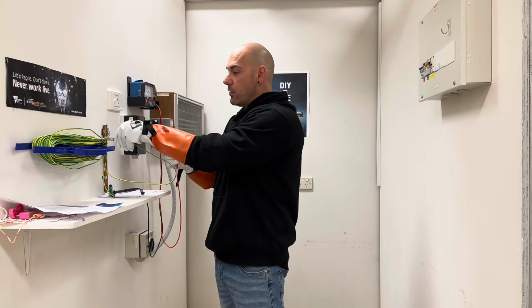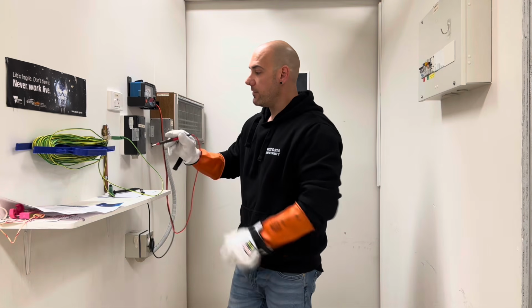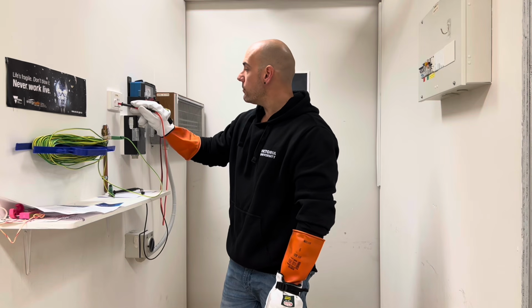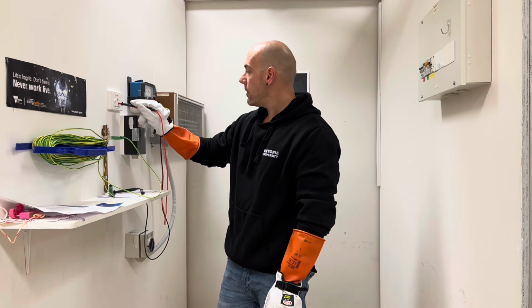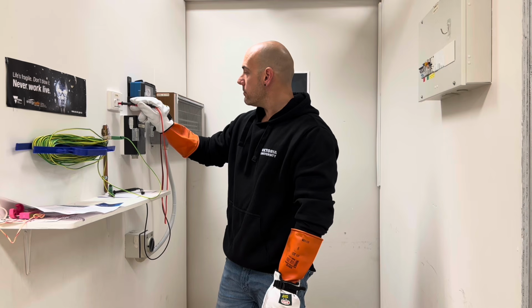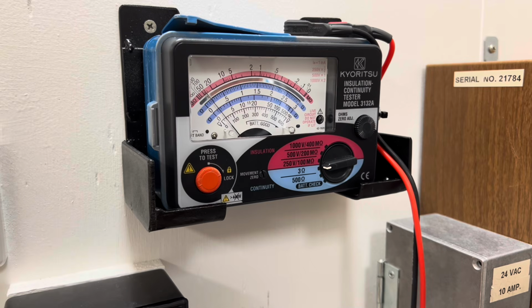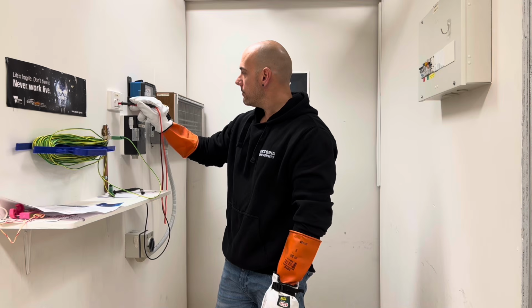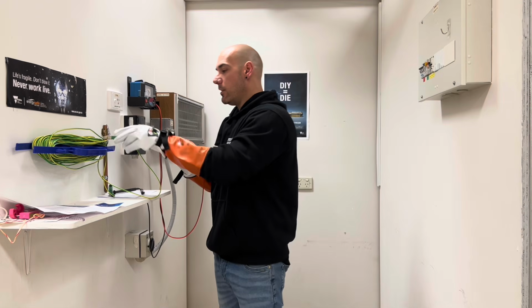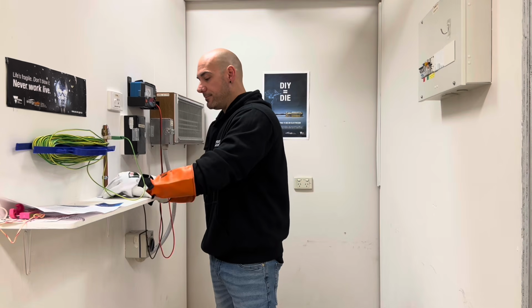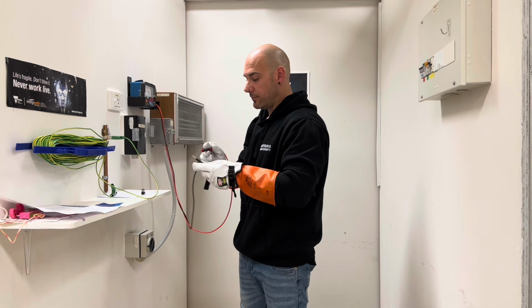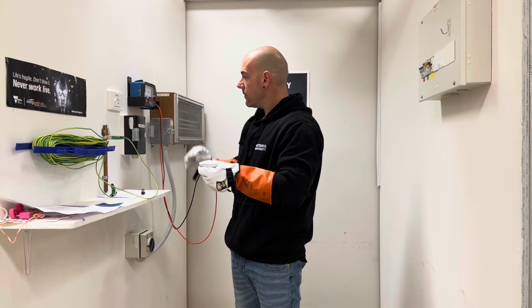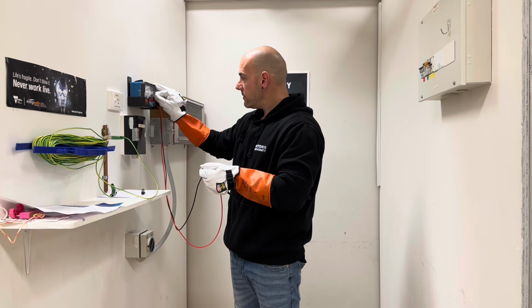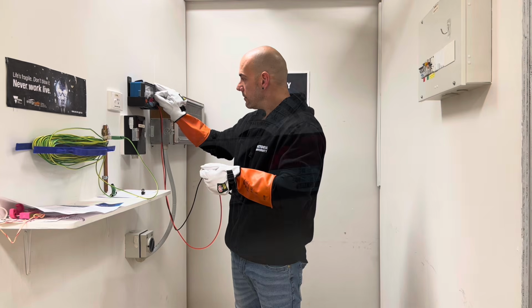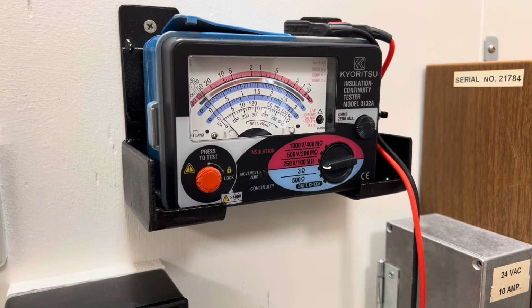We can connect one end of the trailing lead to the earth electrode and one into the earth terminal of our reference earth, and we will get a resistance. We can then disconnect our meter, make sure it's working, recalibrate, and I'm happy that we have an effective earth.